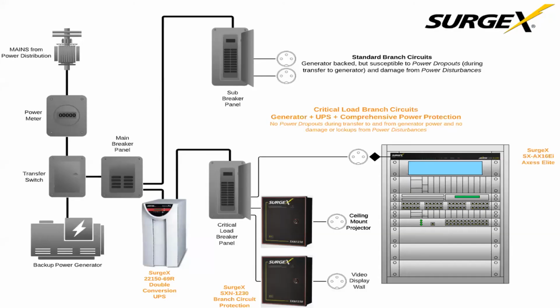Here is an example of such a system, where you can see the mains coming in, going through the meter. You've got a generator in the bottom left corner, which goes to the transfer switch, then to the main breaker. Out of the main breaker, the large format UPSs are hardwired, and the output of that goes to a breaker panel that's on its own.